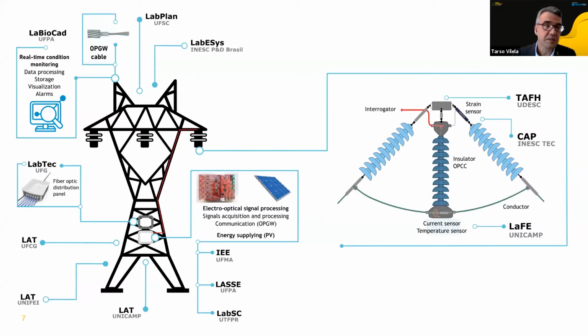At this point, we are using fiber optics through this cable. We also have in the substation the real-time condition monitoring, where we do data processing and visualization, and we can set alarms. In the tower, we have a fiber optic distribution panel, which connects all the optical sensors. All this equipment needs to be powered up, so we have solar panels and the electro-optical signal processing unit, which is this red board. We're going to take a look at it in the next slide.